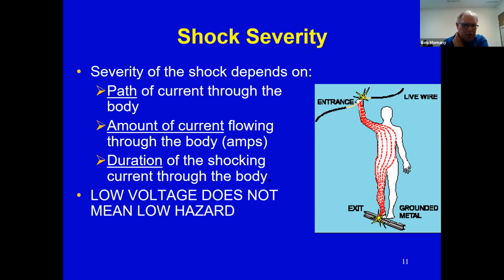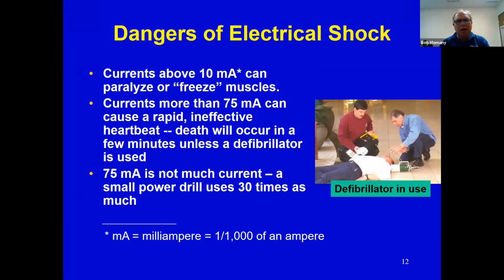I mentioned that low voltage doesn't mean low hazard, and I said I'd get back to that. So here we go: currents anywhere above 10 milliamps can cause muscles to freeze up. Like in old cartoons, where the coyote or Bugs Bunny grabs a wire and can't let go — in reality, that's what happens if there's enough amperage. The muscles freeze up and somebody can't let go.